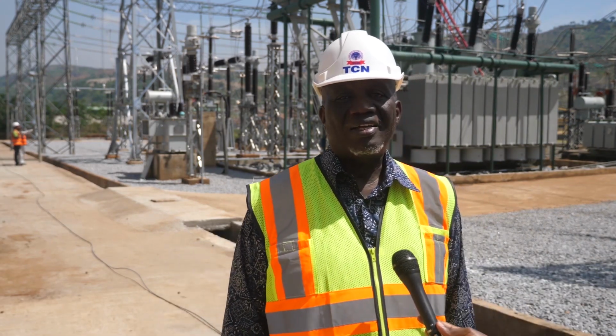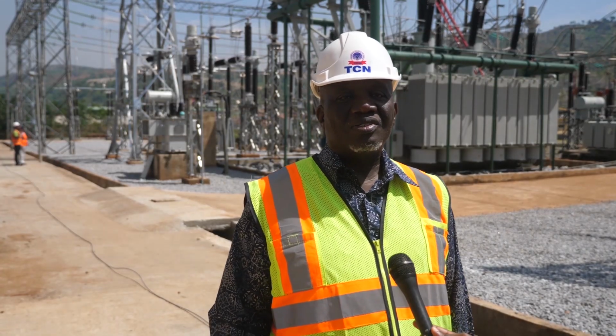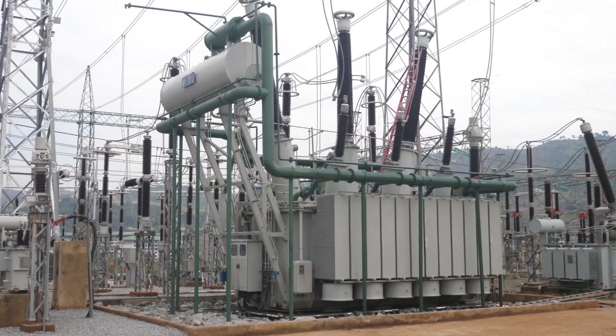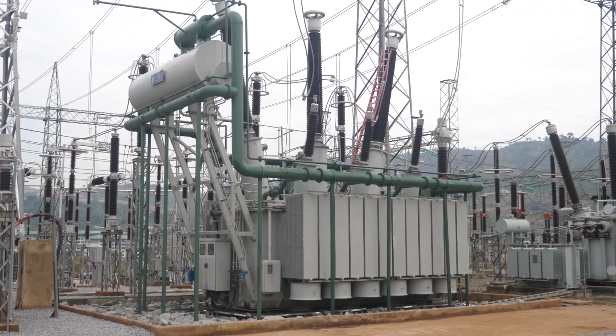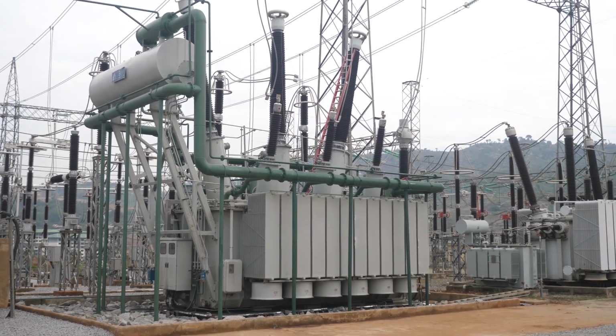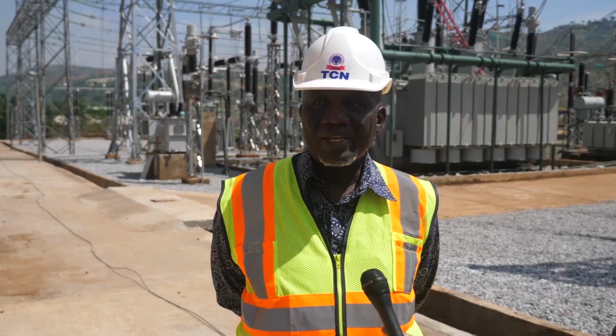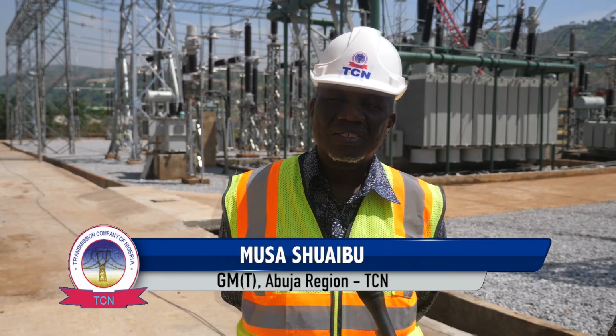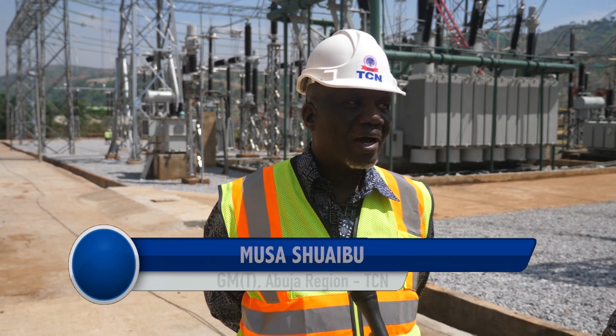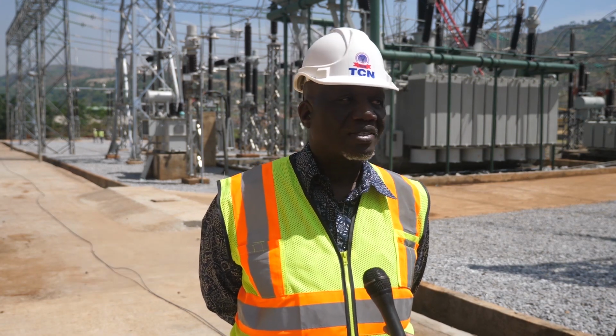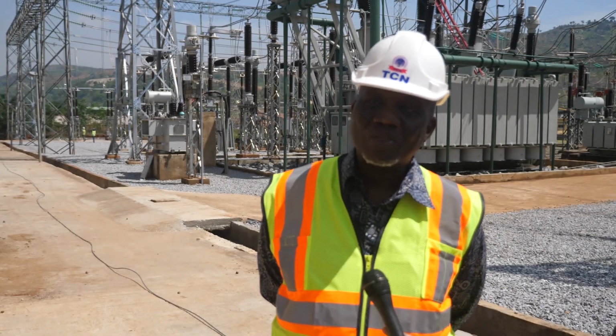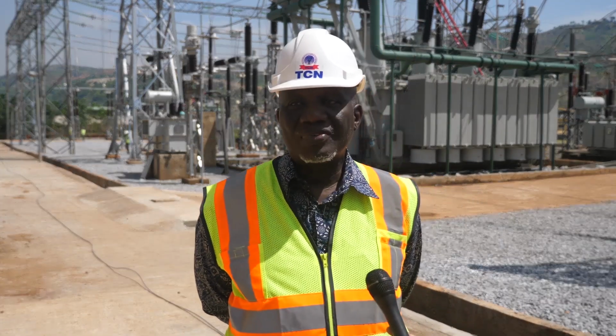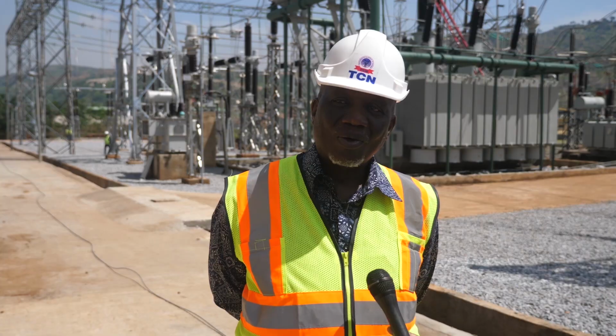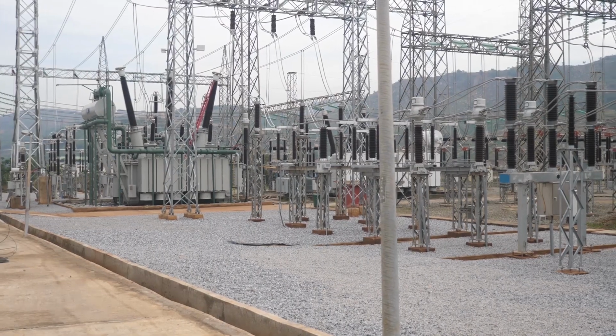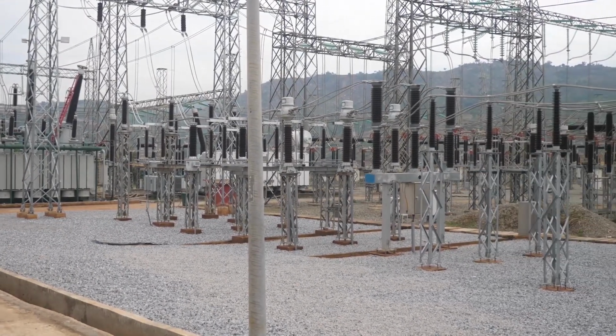He further said that with the commissioning of the new 300 MVA power transformer, the substation's capacity has increased from 450 MVA to 750 MVA. Previously, when we had the 3 by 150, the load was 360 megawatts. Now we're having 300, which translates to 240 megawatts. So the cumulative load now will be 600 megawatts. So you can see that AEDC will now have more load to feed its customers.